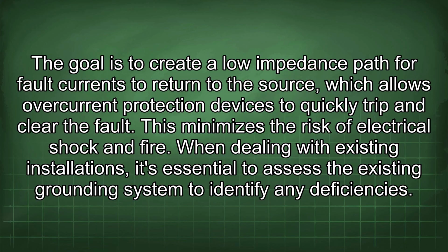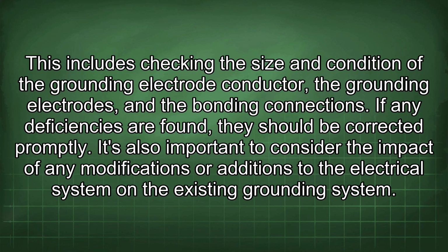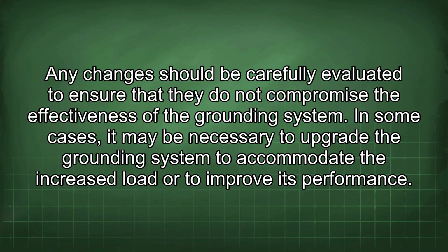When dealing with existing installations, it's essential to assess the existing grounding system to identify any deficiencies. This includes checking the size and condition of the grounding electrode conductor, the grounding electrodes, and the bonding connections. If any deficiencies are found, they should be corrected promptly. It's also important to consider the impact of any modifications or additions to the electrical system on the existing grounding system. Any changes should be carefully evaluated to ensure that they do not compromise the effectiveness of the grounding system.